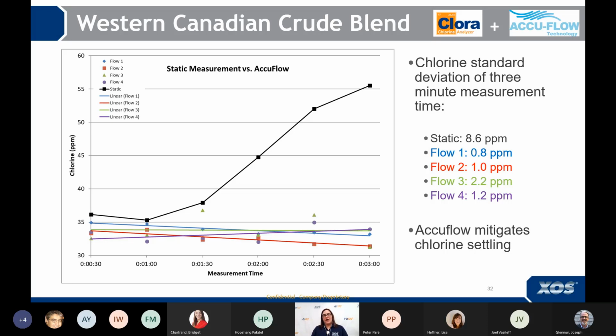But what you'll see here is the AccuFlow basically mitigates the settling of the chlorine. And the way it does this is you take a syringe that's filled with 60 milliliters of crude oil, and it is continuously injected during the measurement time. So the chlorine doesn't have a chance to settle because it's being pushed through the measurement area and then collected on the outside of the analyzer. Okay, so this is one way to handle it.